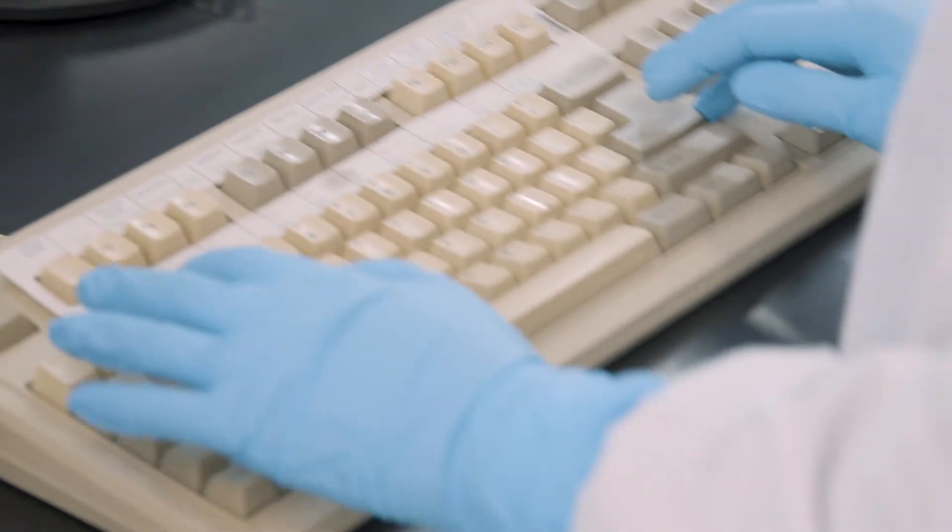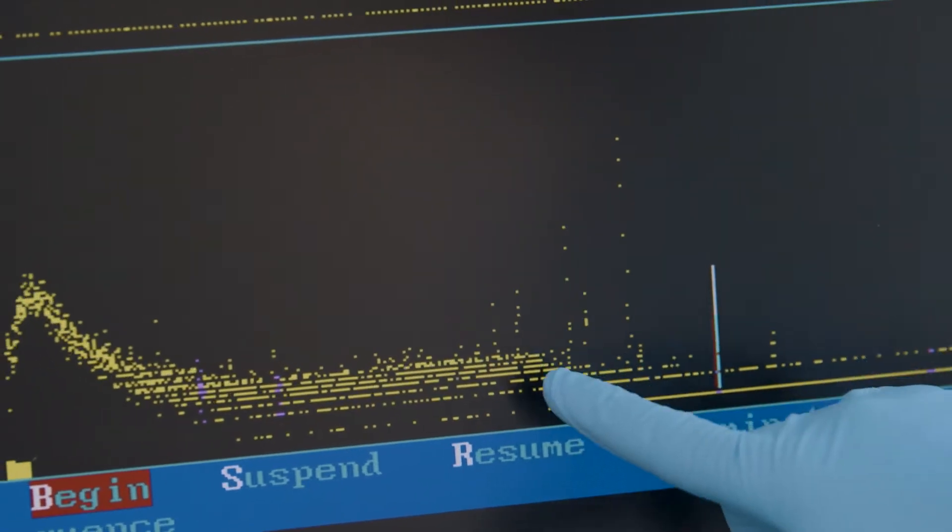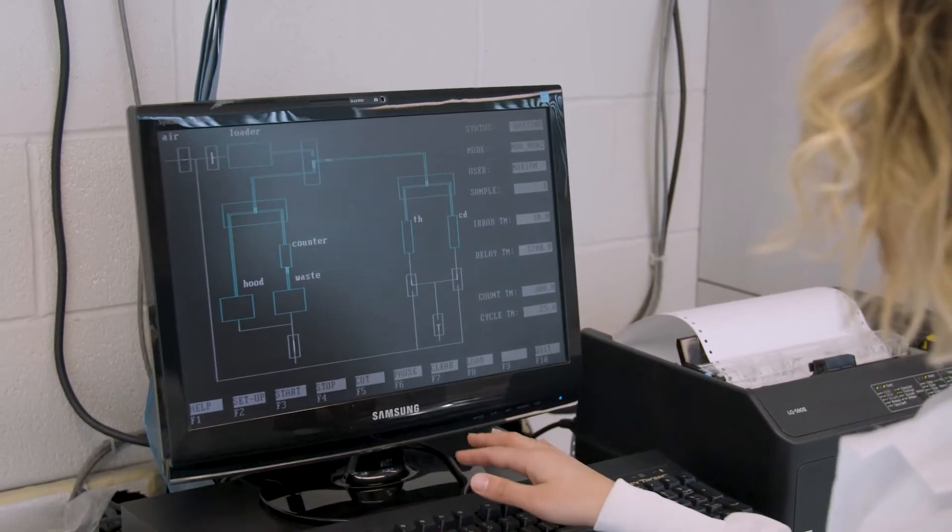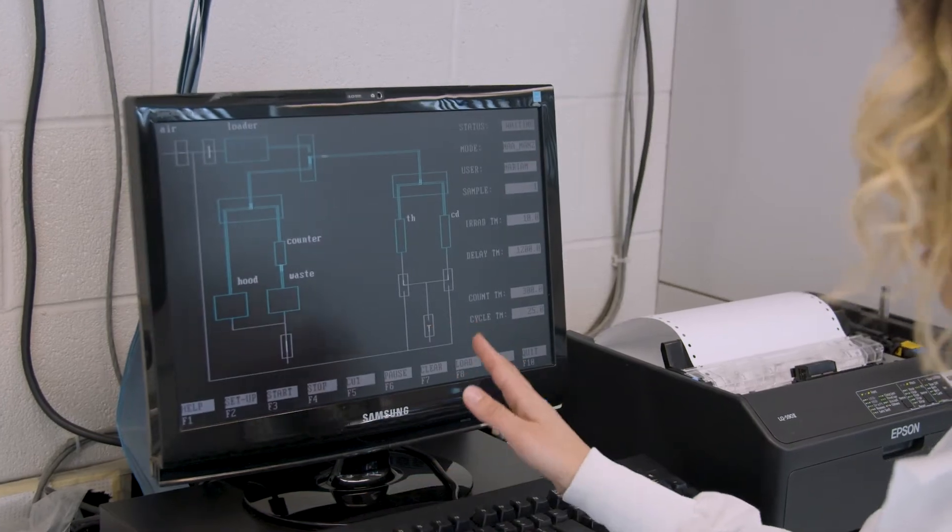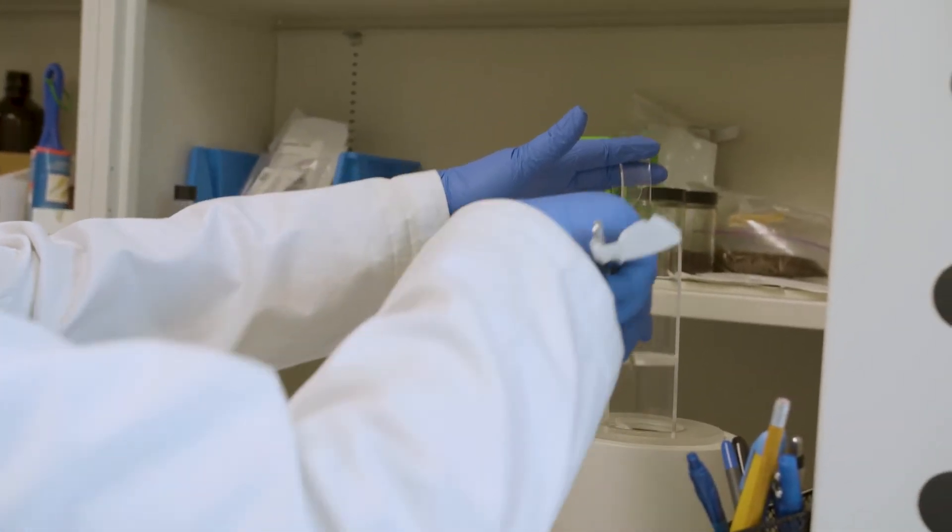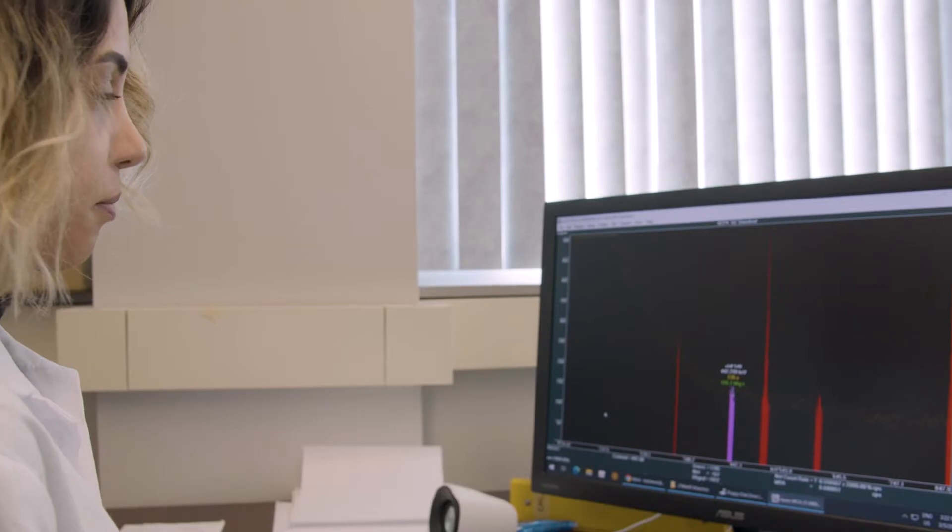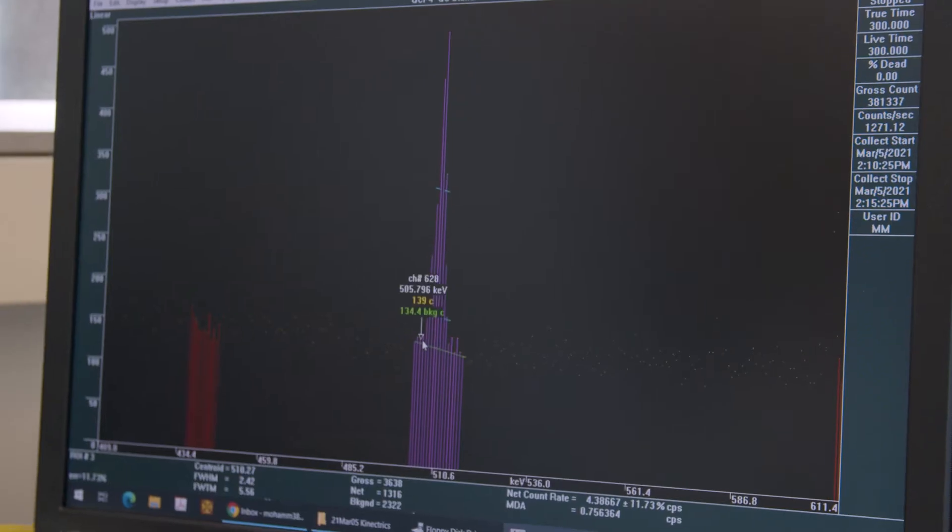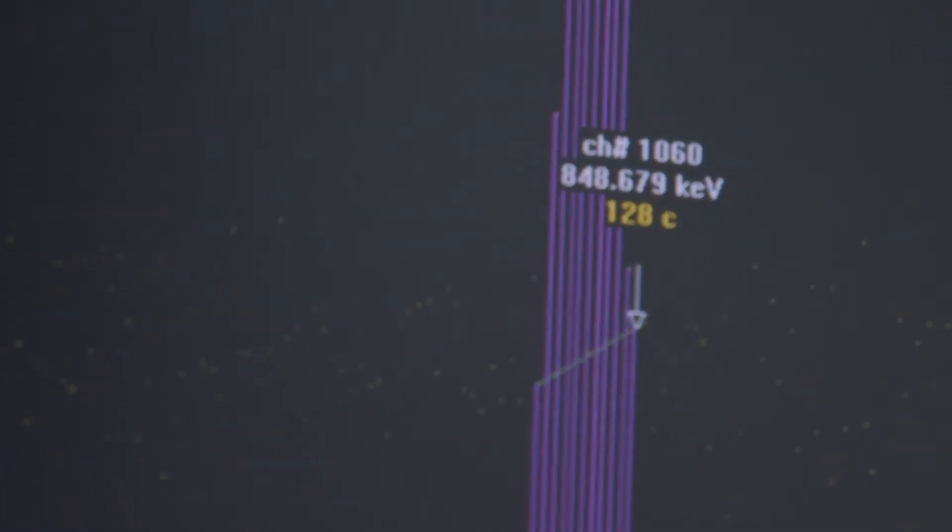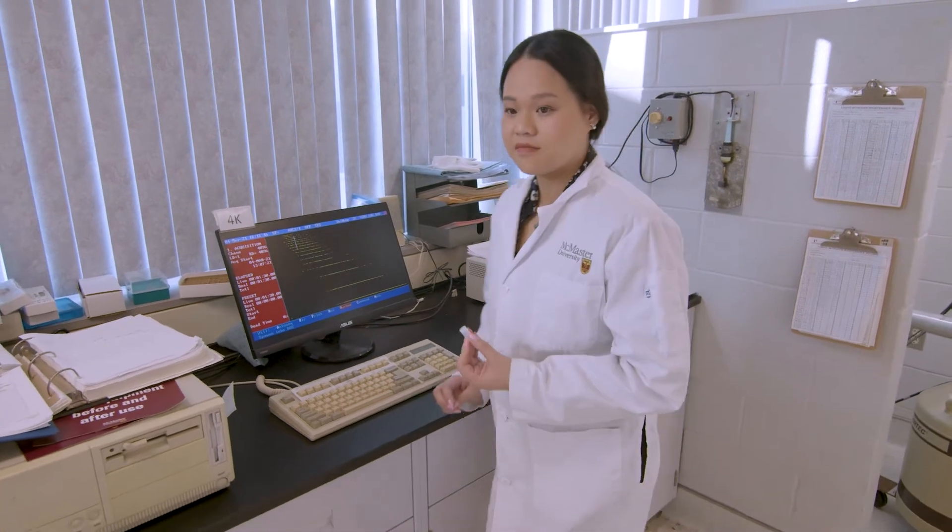Prompt gamma neutron activation analysis, or PGNAA, utilizes the prompt gamma rays emitted during neutron capture rather than the gamma rays that are emitted as a result of radioisotope decay. Used to determine elemental composition, it's useful for quantifying boron, cadmium, and certain lanthanoids. Our labs utilize high purity germanium detectors and their associated counting equipment.